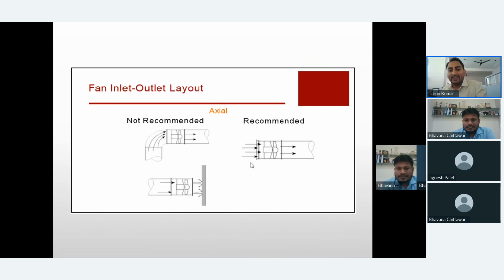Further, in an axial fan, it is always recommended to go from the impeller to the motor side. You will have proper cooling for the motor, and proper casing will be available, so the air will travel a longer distance, the flow will be efficient, and noise will also be lower. And try to avoid any direct obstruction after the axial fan.